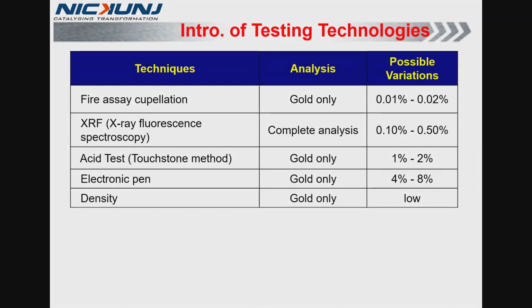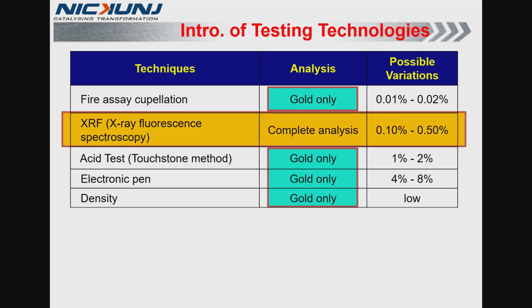Here is a list of techniques practiced in India for gold analysis, showing its range of possible variations. Fire assay technology is most reliable but has its limitations of 5 to 7 hours time consumption and loss of other metals present in gold. Looking at the other methods mentioned in the list, like acid test, electronic pen, and density meter, shows analysis limited to percentage of gold only. Whereas XRF gives you a complete analysis of the metal composition with a reasonably good result in comparison to the other technologies mentioned.